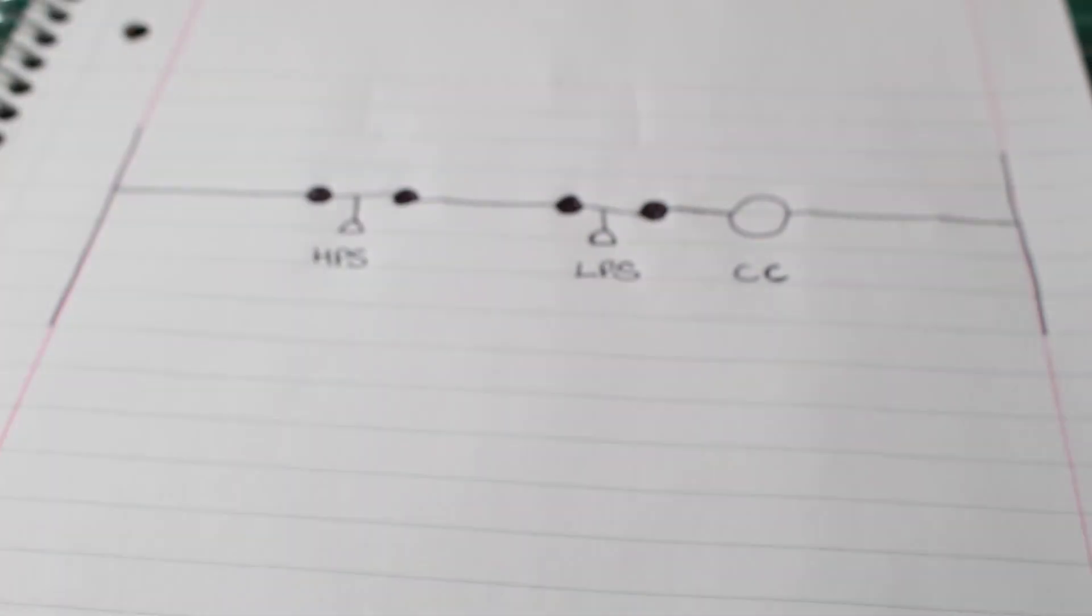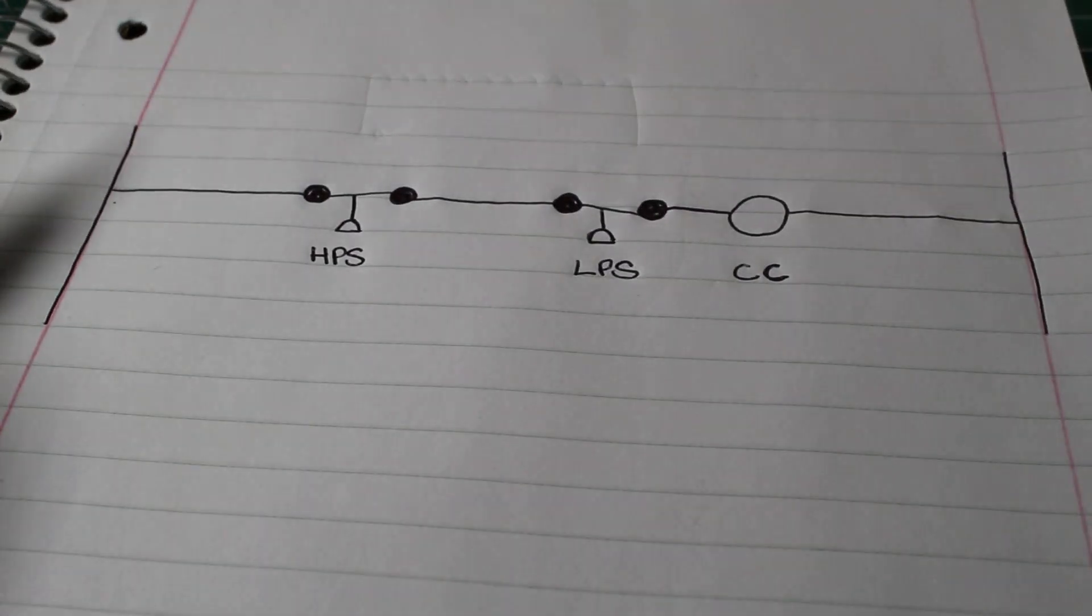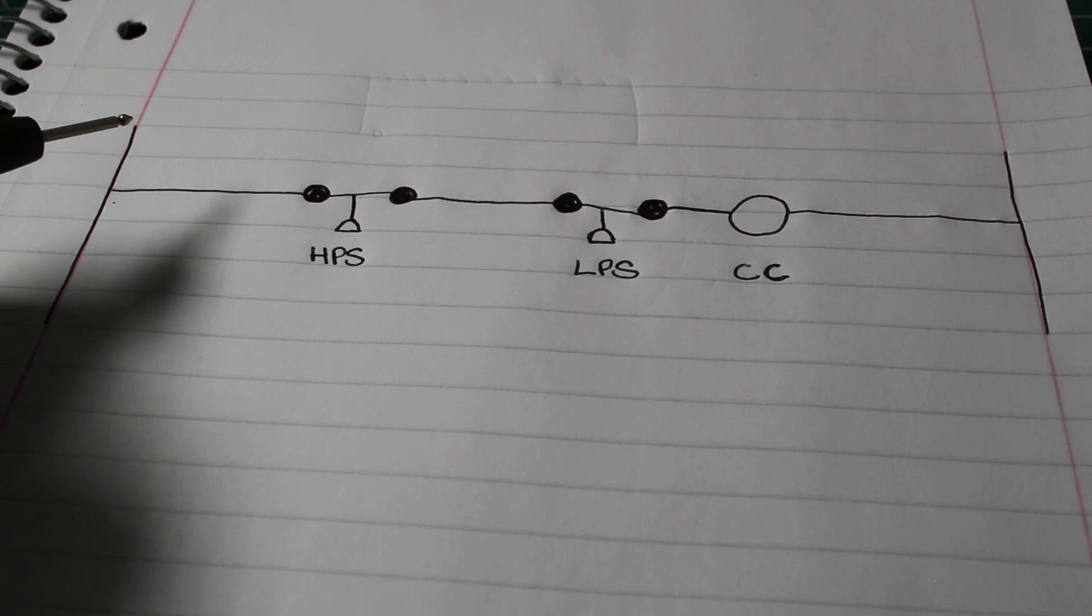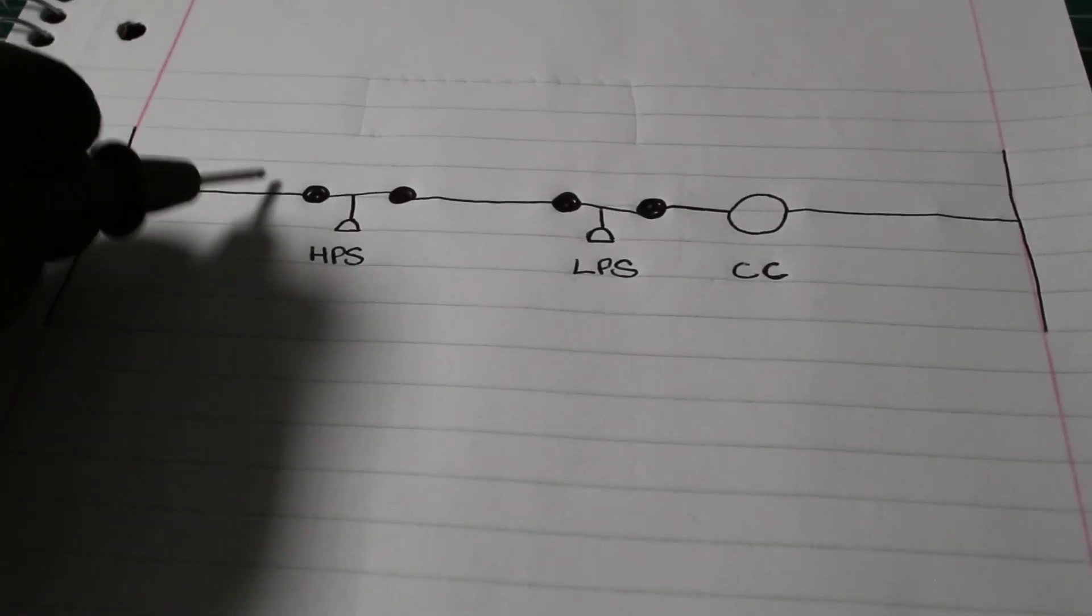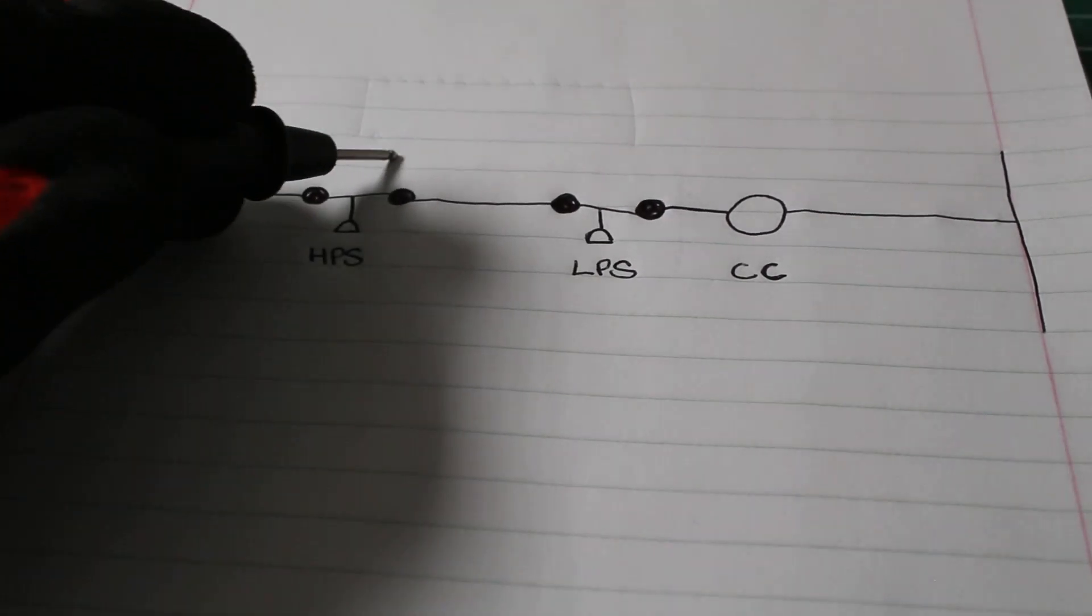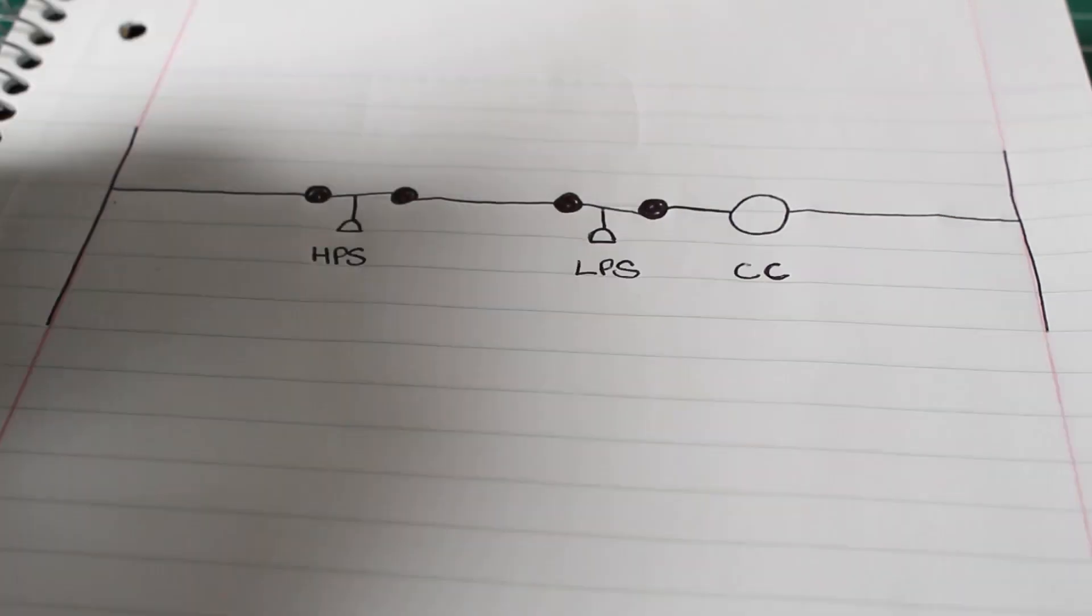So let's say this whole line has electricity and this coil is energized. If we have an event where we have a high pressure situation, this switch will open, thus stopping the flow of electricity to our contactor coil and shut down our equipment.